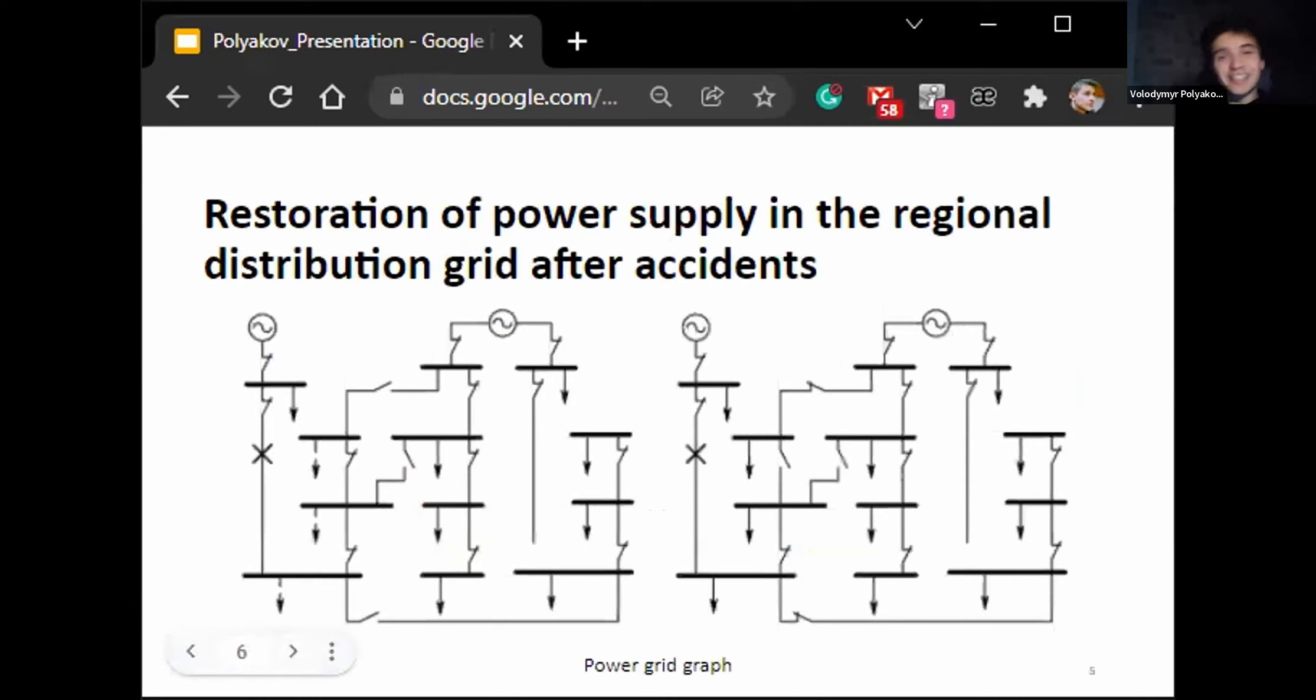For restoration of power supply in the regional distribution grid after accident, you can see an example of power grid graph for such a problem on the slide. In the left part of the figure in the normal state, all the loads are distributed between two power centers. There are no cycles or powered lines. When an accident occurs in such power grid, three consumers marked with dashed arrows are de-energized. The situation of power supply restoration when all three disconnected consumers cannot be powered from one power line due to overload is shown on the right. In this case, the de-energized section is divided into two parts by opening the circuit breaker that is normally closed. After that, it becomes possible to power de-energized consumers from different lines of the working part of the grid.